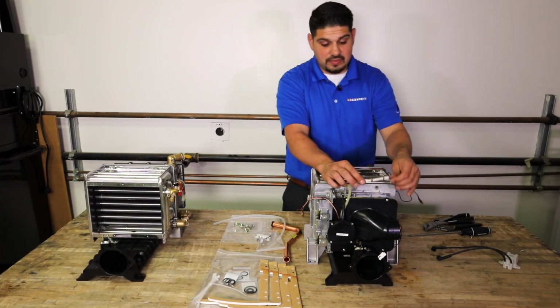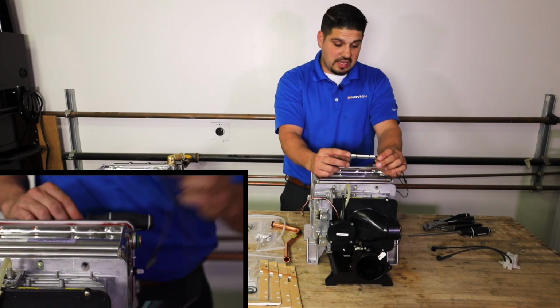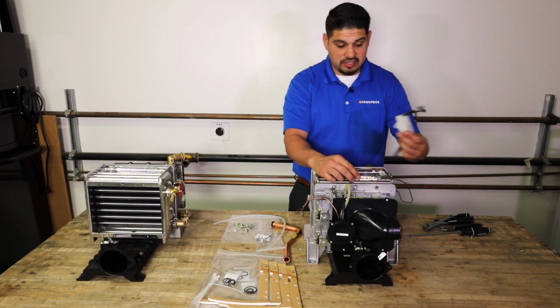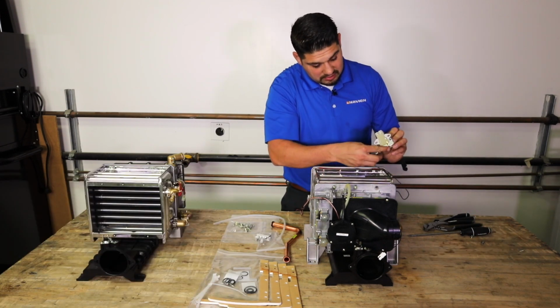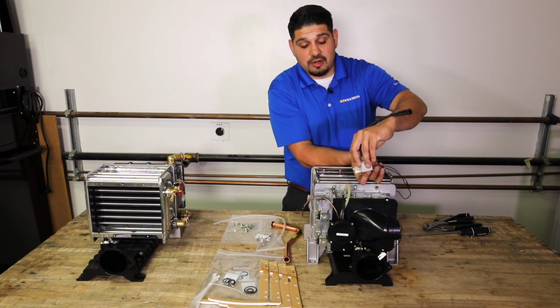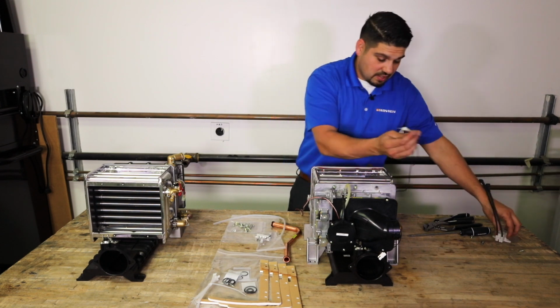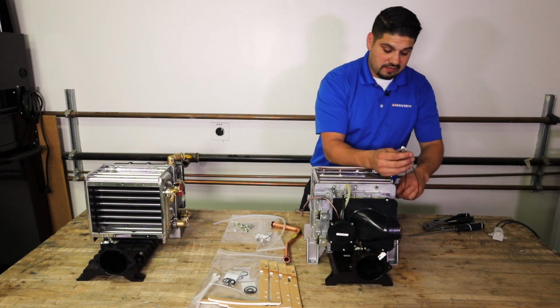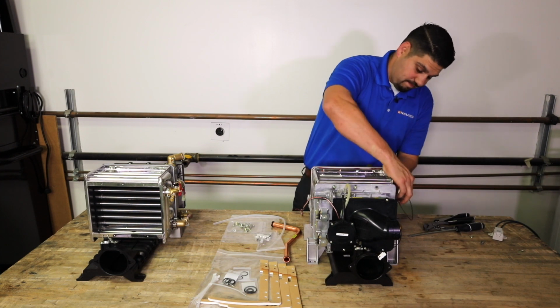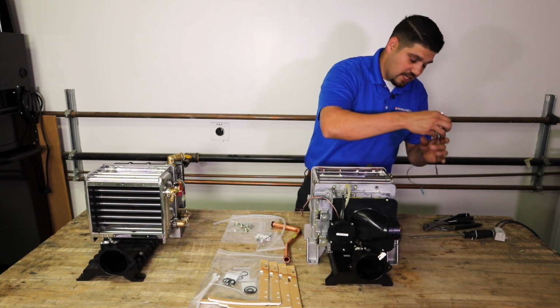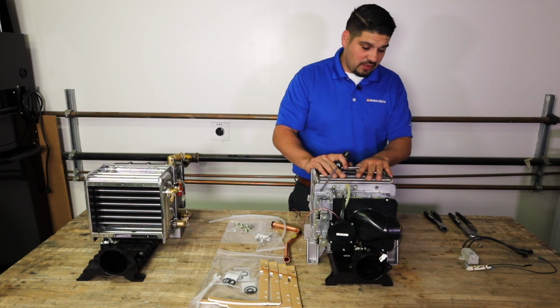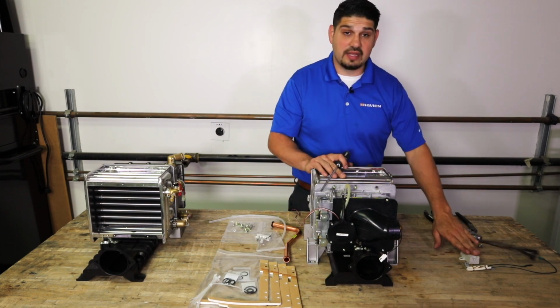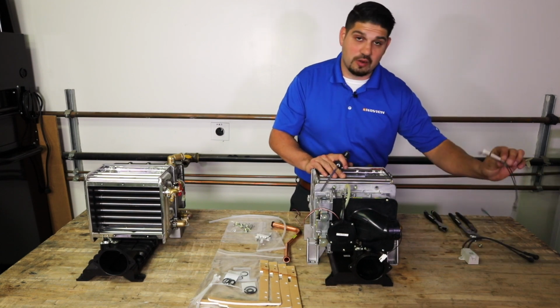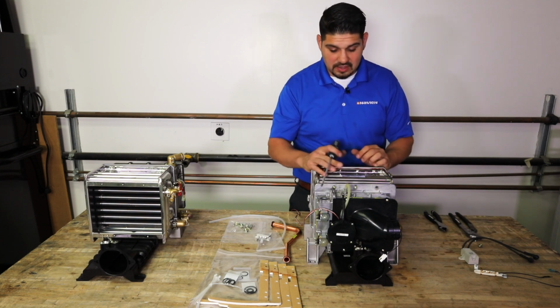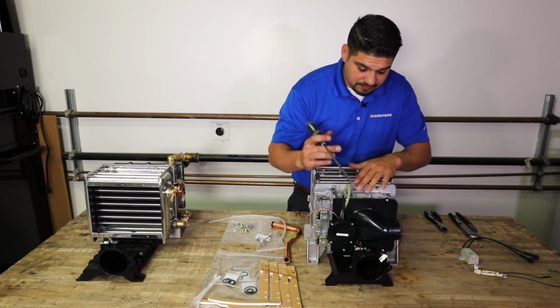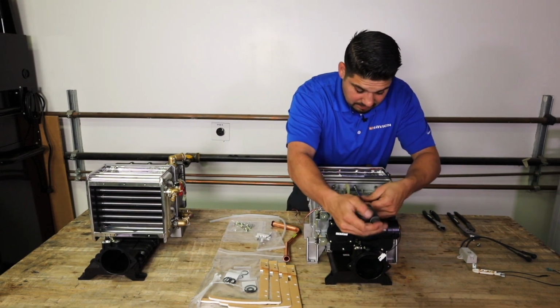Right below it, you have your thermal fuse. And the screws that hold on your ignition transformer, I'll try to show it to you. It's going to go like that onto your burner. So you're going to take this off. Following that, you're going to have to remove your thermal fuse. I'm going to reuse that over there on the other unit. Now that we have removed our ignition transformer and our thermal fuse that was right behind it, we are going to take off the burner.